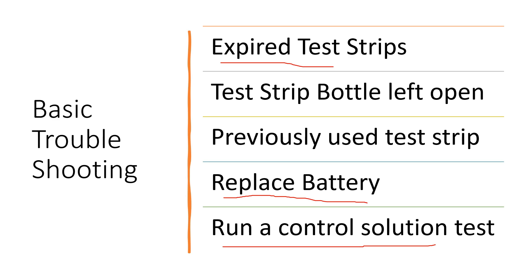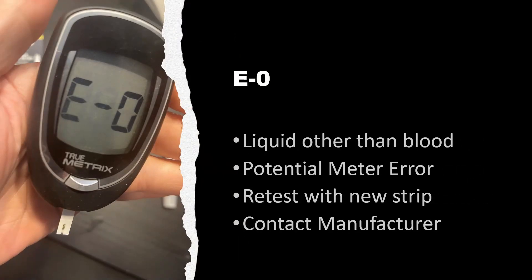E0 means a liquid other than blood was used to do the reading, or a potential meter error. Use a new test strip and try retesting. If this continues to occur, you can contact the manufacturer — the number is found on the back of the meter.